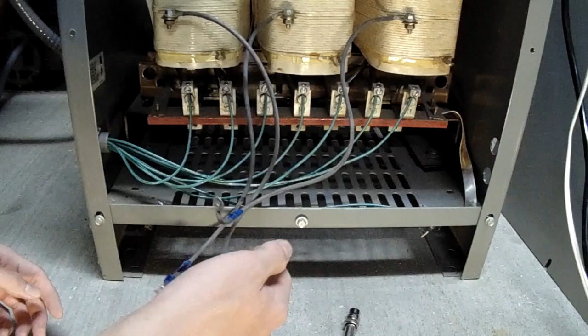I'm going to go ahead and explain how I'm going to do this, but just a couple recommended configurations. If you still want to be able to use this transformer for its original intended purpose, the star and delta configuration, then you might want to put these leads on a contactor and wire the contactor in such a way that in one position it will keep the transformer in its original state, and in another position, on or off, whichever you choose, the contactor would set it up into the star configuration here, so you can have more or less choices for how you wire it. So now I'm going to put these lugs all together on one of these coils, and then I'll add a wire, and that will be our new neutral for that star configuration.